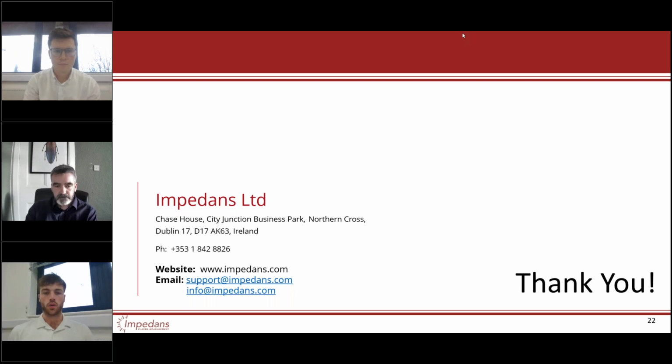Yep, and I've just got a last couple of questions. Another one for you, Angus. The Impedans substrate level sensors, do they have spatial resolution? Yes, in that the substrate level sensors have several sensors built into them. So the spatial resolution is basically the distance between the sensors. We have a 300 millimeter sensor that has 13 sensors on it. The spatial resolution is the distance between the sensors. It's of the order of tens of millimeters. So it's not like millimeter resolution. It's basically the positioning of the sensors.